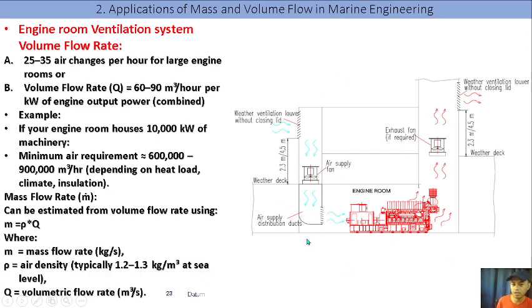Okay, so here we have a picture of our engine room. Since the engine is hot, we have an air supply fan here, and an exhaust fan here, used if required. But usually on a ship, to maintain 25 to 35 air changes per hour and maintain the volume flow rate needed by our machineries, these exhaust fans are made to work as supply fans since they are reversible.